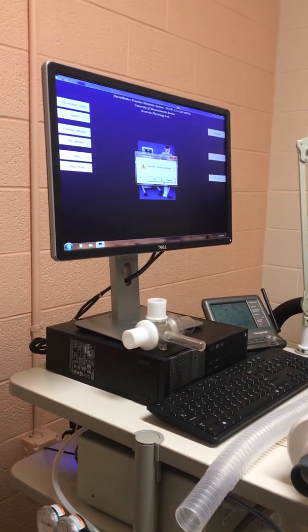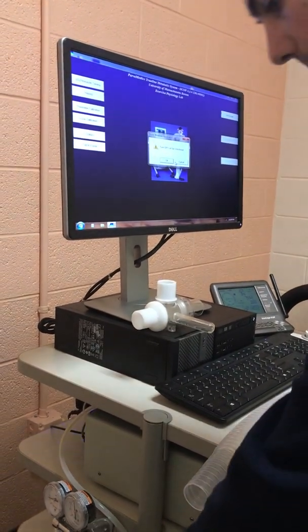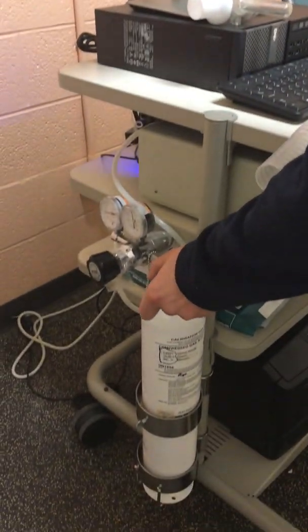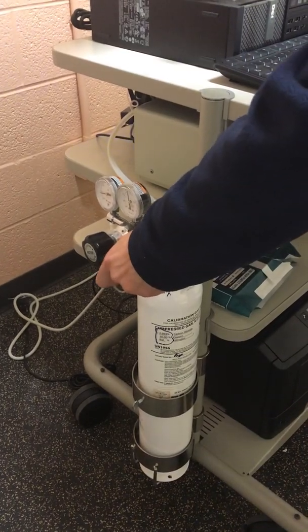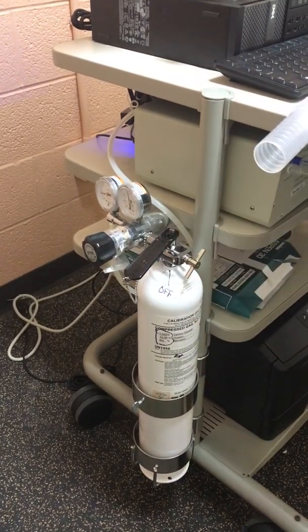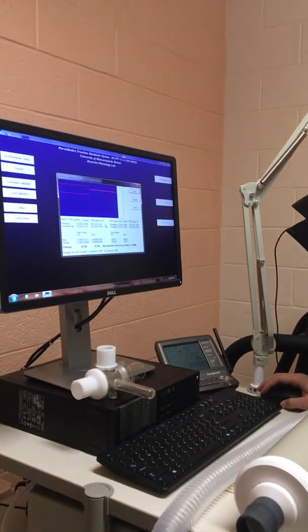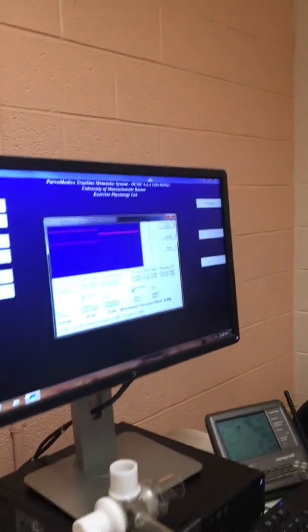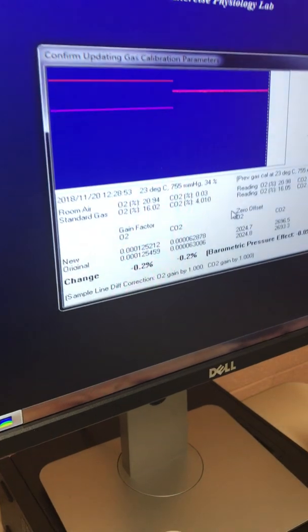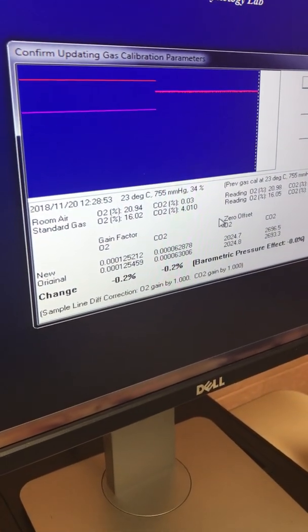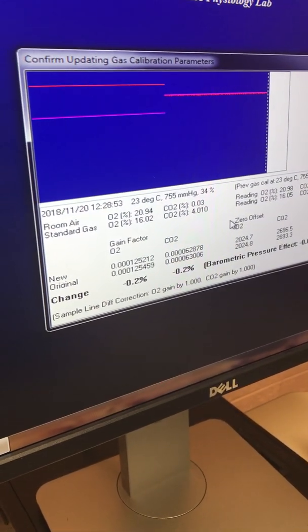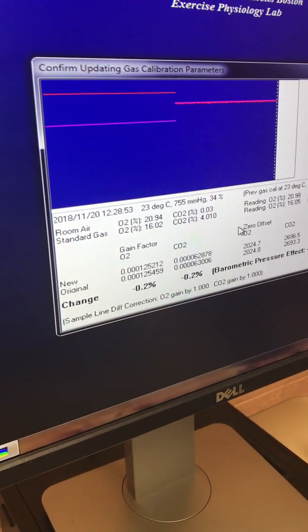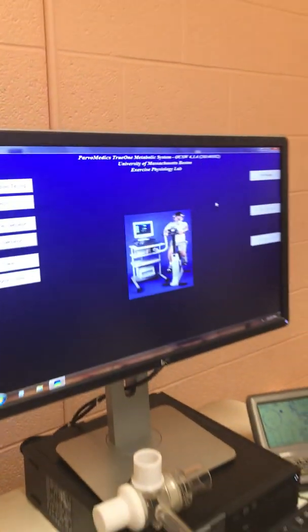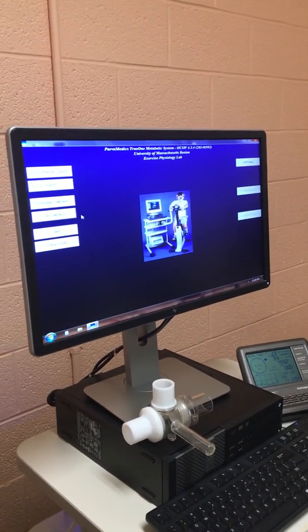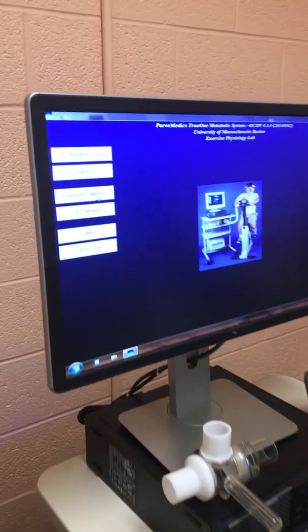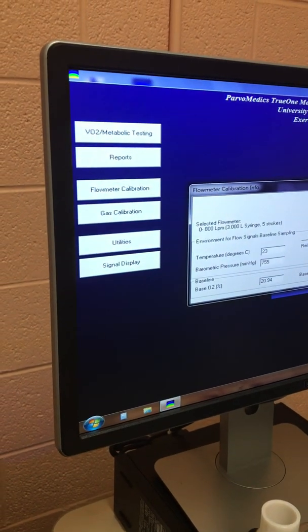Going through another sample, so we can turn off our gas calibration, and we're going to turn it off and make sure not to turn it too far because this is sensitive. So turn off gas calibration, and here we can see a negative 0.2% change, and we're just looking to make sure it's no greater than 3%. So we can move on. This is acceptable, and we'll save this reading. And so the gas calibration is complete, and we'll move over to flow meter calibration.